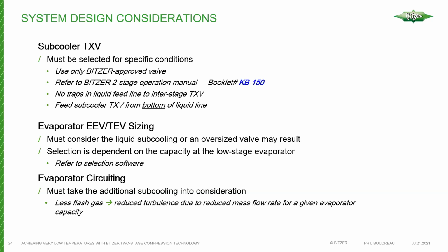The other thing is, when designing systems that are going to use a two-stage compressor in a subcooling mode, it's very important that the manufacturer is aware of the subcooling. For example, you may buy a condenser unit from a manufacturer, and maybe you're buying some special type of coil that has to be made up. It's extremely important they know about the subcooling. The more subcooling you have, the less flash gas in the evaporator leaving the expansion valve, which results in lower turbulence, which in turn leads to less heat exchange, which could lead to laminar flow. In this case, you're going to have a hard time getting the heat from the heat source into the refrigerant through the evaporator. So it's very important that subcooling is always considered.